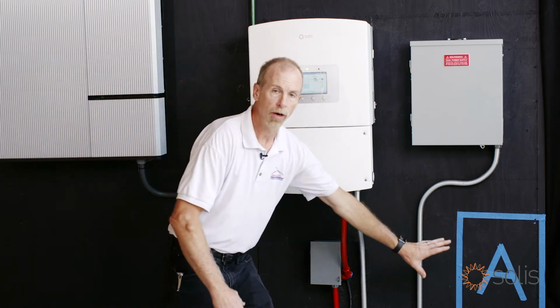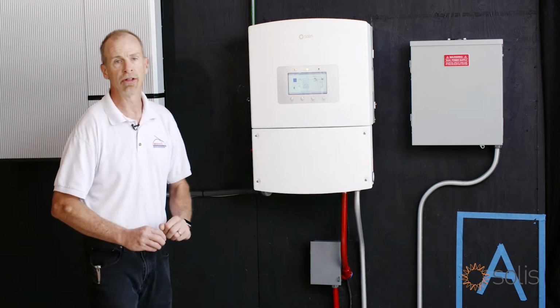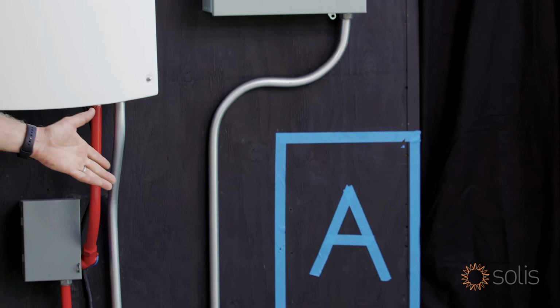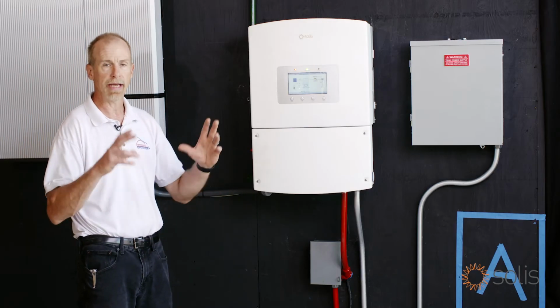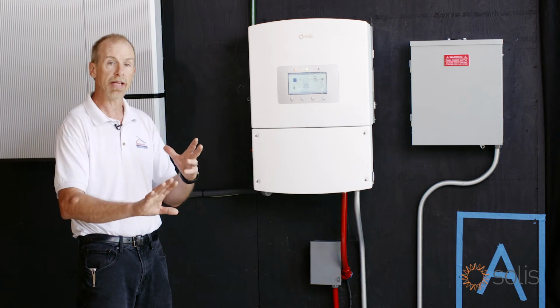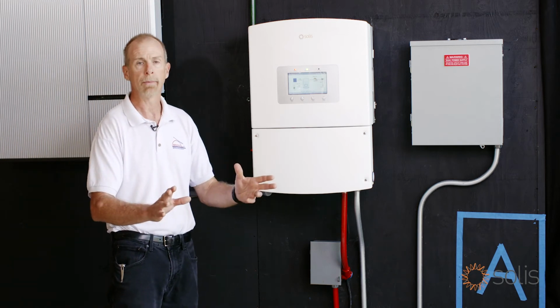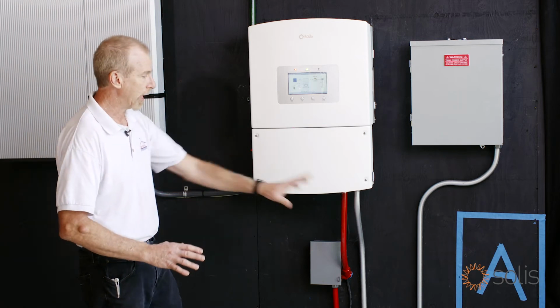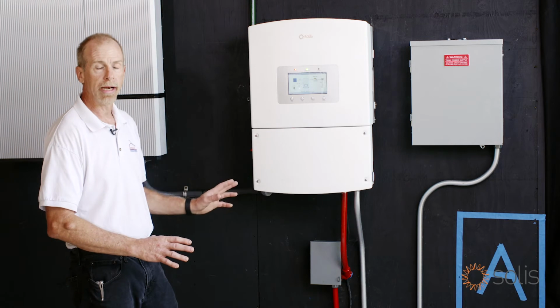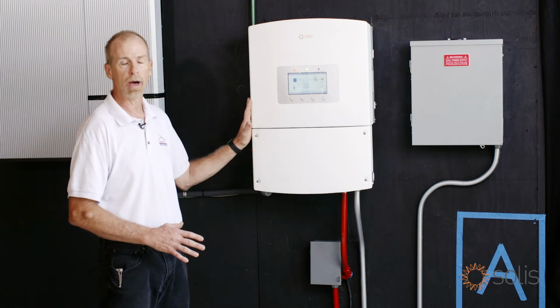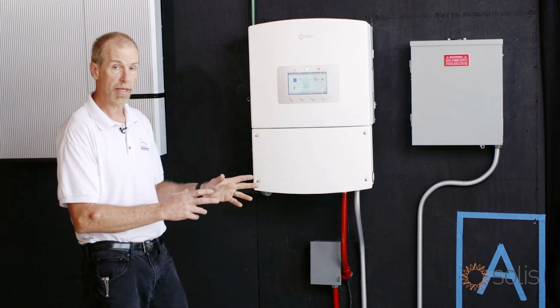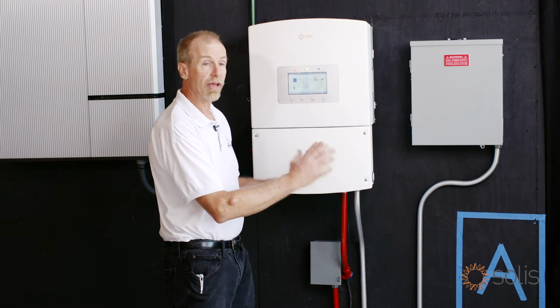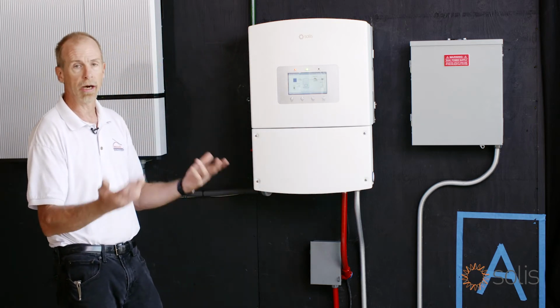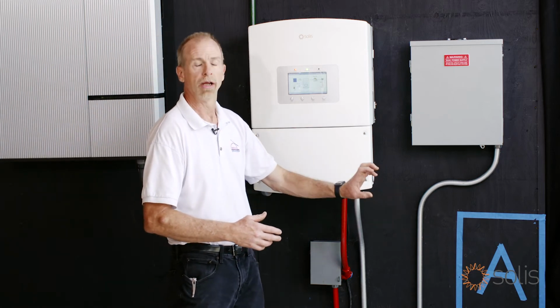So over here we have an area where we've selected to install our auto transformer. This is just simply a transformer. It doesn't do anything other than take the power at 240 volts and supply us a center tap neutral in 240 for 120 volt circuits. The ratings on this transformer are the full ratings of the backup power system. So this 10 kilowatt inverter has the capability of 6 kilowatts in backup power. Not 10 kilowatts, but 6 kilowatts. And this transformer can provide 6 kilowatts on either side of the 120 volts or split, depending on how we do it. So that's a 6 kilowatt auto transformer.